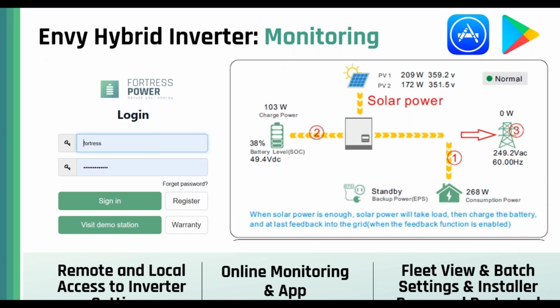With this system, it has a fleet view and batch settings. Let's say you have multiple installations with the same configuration, for example 4 or 5 sites with 3 E-flexes and 1 Envy inverter. With the batch settings, you can just select all those systems and make your programming, assuming they're connected to the internet, and configure all of them at the same time. I want them all to be fast zero export, using these time of use, charge first PV.